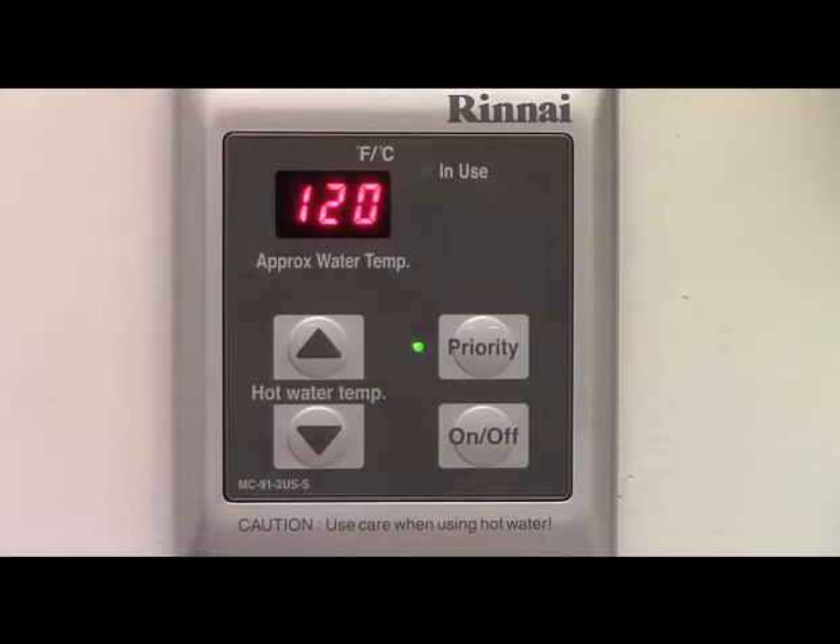In this segment, we'll discuss the priority function. Priority consists of a priority button and a priority indicator lamp. Priority comes into play primarily when multiple temperature controllers are connected to a single water heater. Up to four controllers can be connected to a single Rinnai tankless water heater, allowing the user to locate a temperature controller close to their point of use so they can conveniently set different temperatures for different uses in different locations. Only one output temperature can be set at a time, and the priority indicator will be illuminated on the controller that is currently being used to set the output temperature.